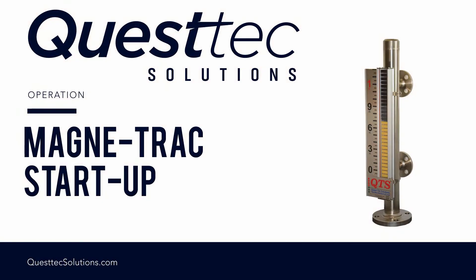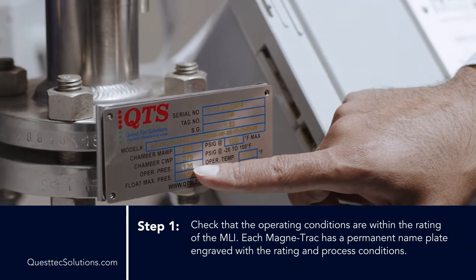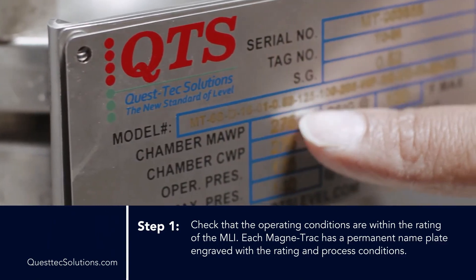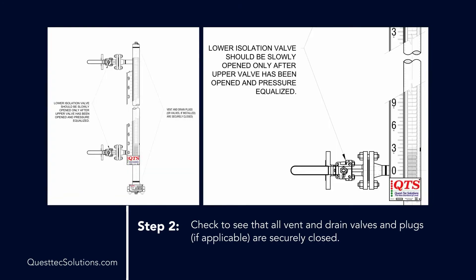Magne-Trac operation — let's put the MLI in service. Step 1: Check that the operating conditions are within the rating of the MLI. Each Magne-Trac has a permanent name plate engraved with the rating and the process conditions. Step 2: Check to see that all vent and drain valves and plugs, if applicable, are securely closed.